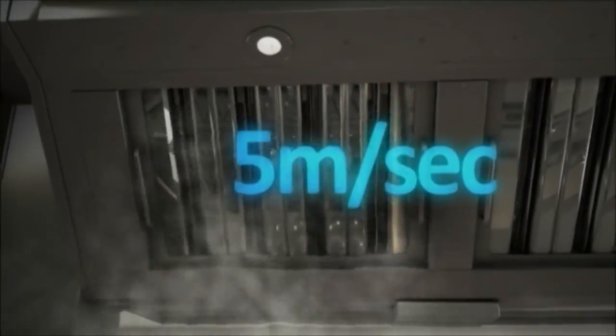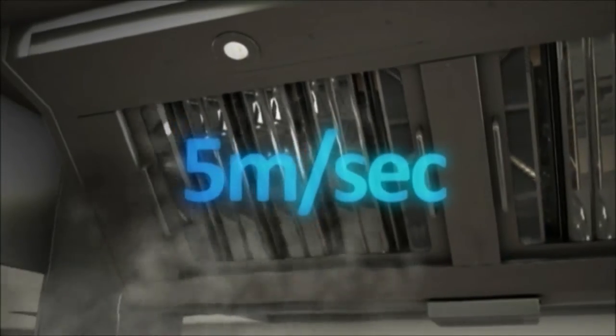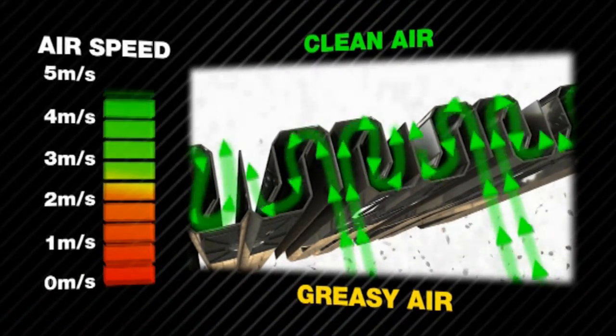Grease baffle filters used in commercial kitchens work on the principle that air should pass through the filter at a constant speed of 5 meters per second. As the air mixed with grease particles from cooking passes through the filter, it undergoes a number of abrupt changes in direction.